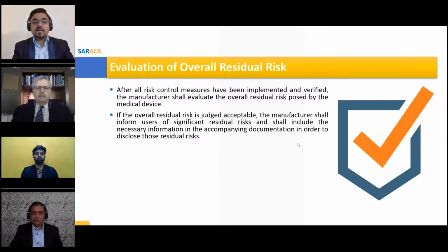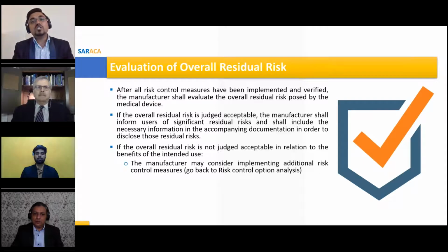If the overall residual risk is acceptable, then the manufacturer needs to disclose all the residual risks in the accompanying documentation. I already told you the accompanying documentation is the documentation that goes with the device to the users, from installation to the decommissioning phase. So if those are acceptable, you need to disclose all those overall residual risks in those documents.